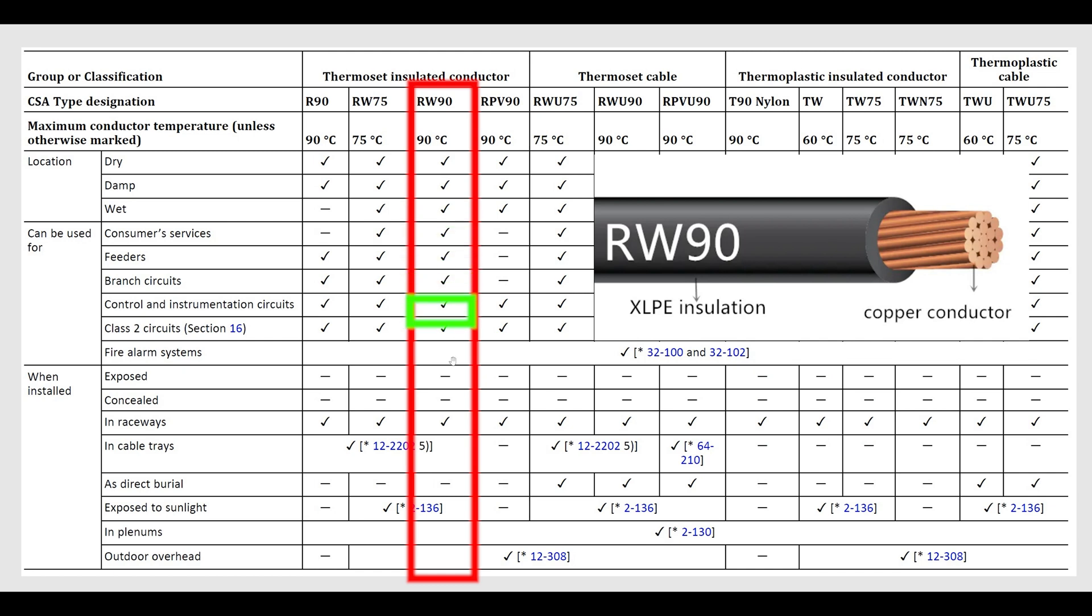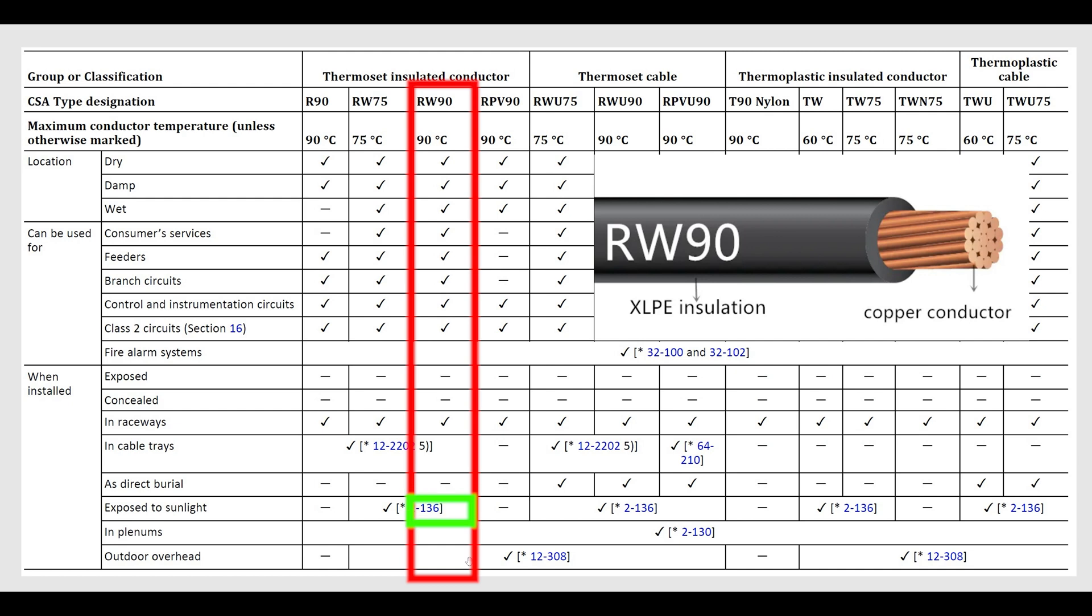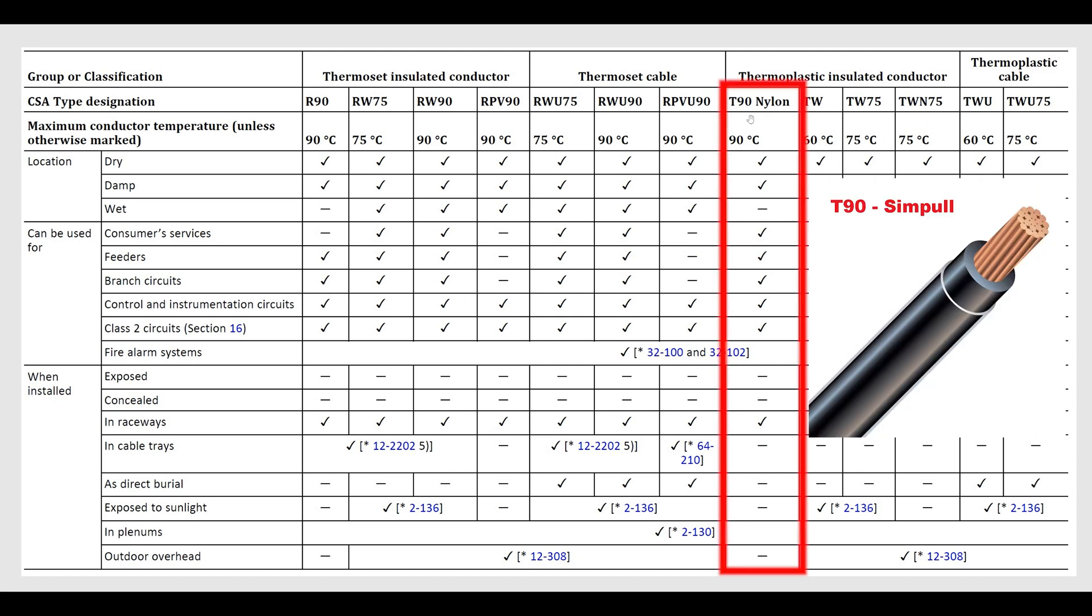It can't be exposed, however, or concealed—what it can be in is raceways, can be in cable trays, can be exposed to sunlight under certain conditions, and can be outdoor overhead as well. So that's just how we read this chart. Also got T90, very common. T90 nylon also can be used in most places, not wet locations though, but definitely dry and damp locations and in raceways.